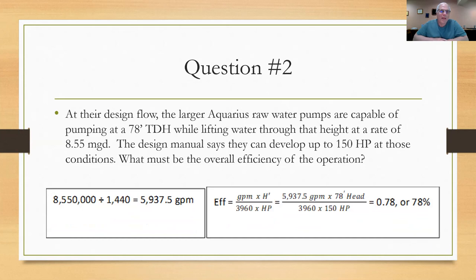I converted that 8,550,000 gallons per day divided by 1440. I come up with 5937.5 gallons per minute and you need that for your horsepower problem. When I was not looking for horsepower because they gave that to me at 150, I'm looking for the efficiency. So I switched those out. I took the efficiency out of the denominator and put that on the left side of the equation, brought my horsepower down to the denominator and worked through, plugging in the numbers, and I come up with a 78% efficiency. Hope you got that because you're going to need it for the third problem.